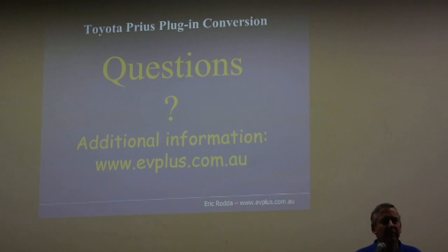Have you got, with your BMS, a maximum discharge rate set into it? The question was, do the BMS modules have a maximum discharge, like a balancing current? It's fixed - the BMS modules bypass at around 600 milliamps, which is about the same current as the end of the charge cycle. All they do other than that is monitor the voltage on the cell.